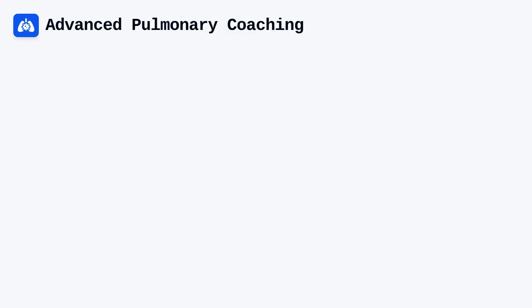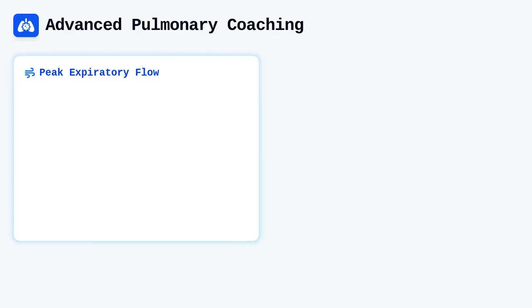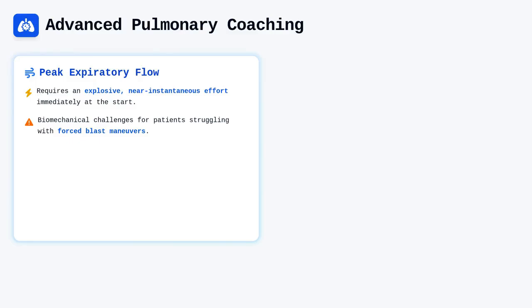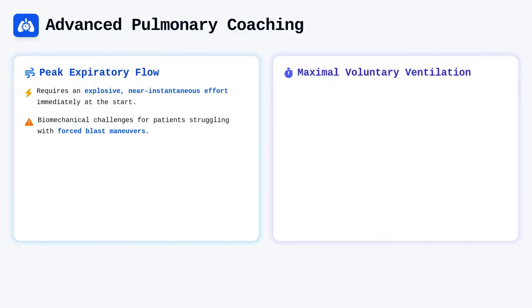Beyond basic forced vital capacity maneuvers, you must also be capable of coaching for the peak expiratory flow and maximal voluntary ventilation. Peak flow requires an explosive, near instantaneous effort from the very start of the maneuver, which can be difficult for patients who struggle with the biomechanics of a forced blast. The maximal voluntary ventilation maneuver is uniquely demanding, requiring the patient to breathe as rapidly and deeply as possible for a sustained 10 to 12 seconds.